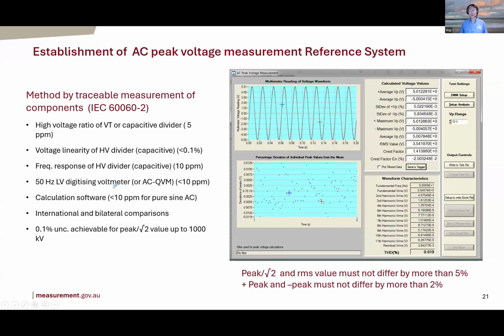And then you got to evaluate your digitized voltmeter. And some people, I can see the Europeans use AC quantum voltmeters and calculation software. You also need to verify your software because these are not pure sinusoidal. They got harmonics and different funny waveforms. So by doing all of these and comparison, you can easily already achieve 0.1% CMC for peak voltage up to 1,000 kV.